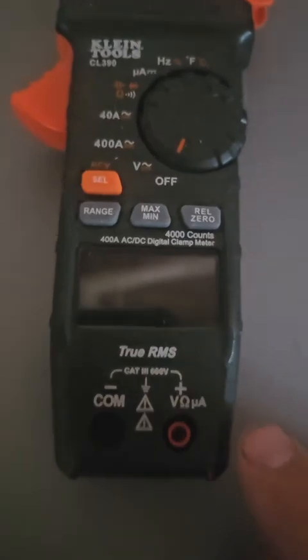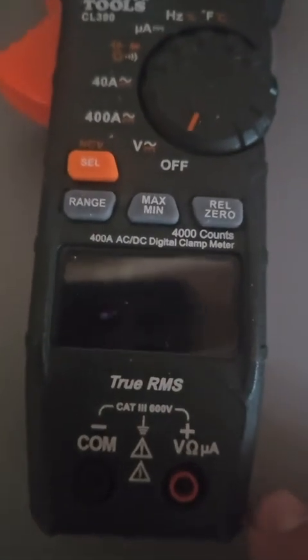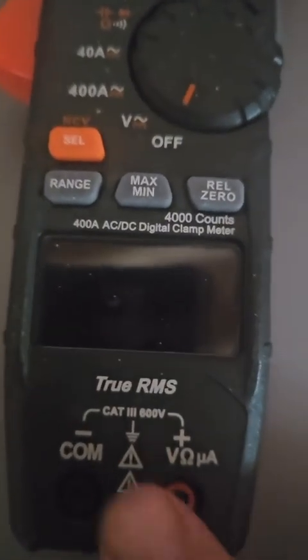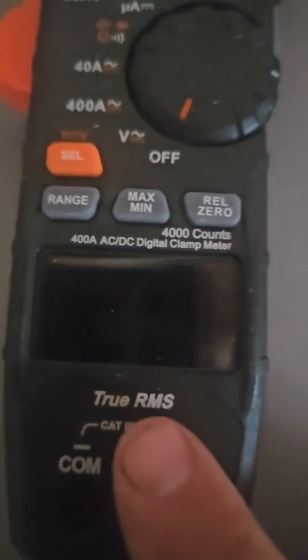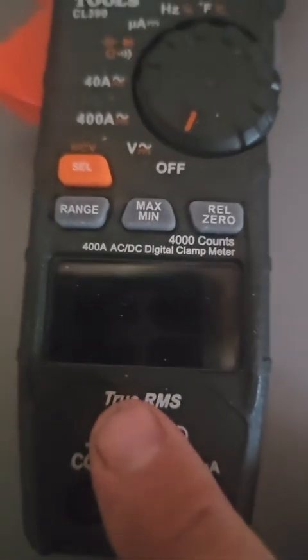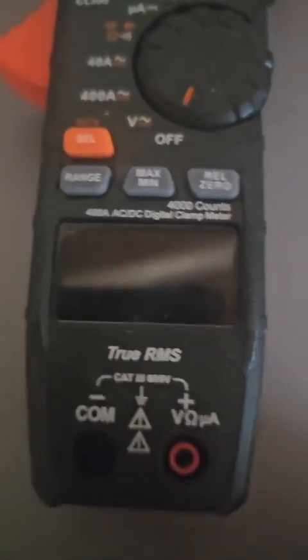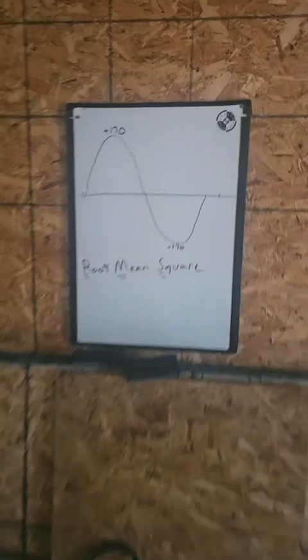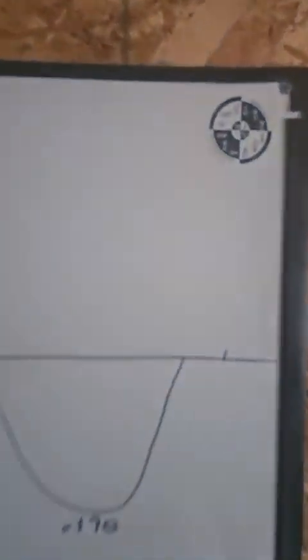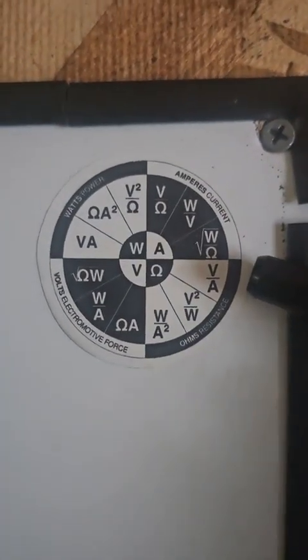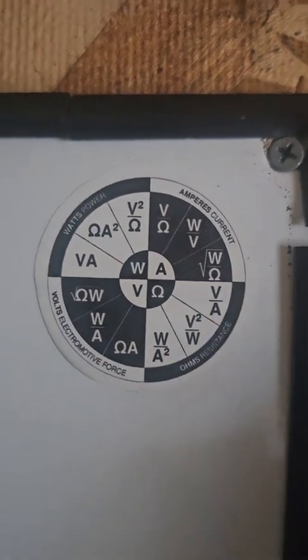120 volts is the RMS value of that wave. Your electrical meters will give you the voltage displayed in RMS, and most of them are labeled as RMS. There's a difference between true RMS and RMS. But once you have the RMS value of the wave, you can plug it directly into Ohm's law or your power wheel, just like you had a DC value.